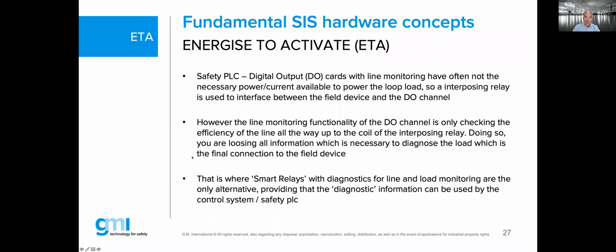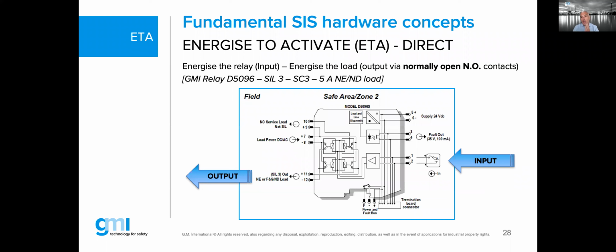So, if you have your digital output with line monitoring, as already mentioned, and you're using that interposing relay, that's sometimes being lost because your digital output stops all the way to the coil of your interposing relay. We want to carry this over all the way to the coil of your solenoid. And that is where the interposing relay with that smart functionality will be certainly a necessity, or let's say it will be necessary to have this functionality enabled to use that functionality benefit. And that's what I will show you over here.